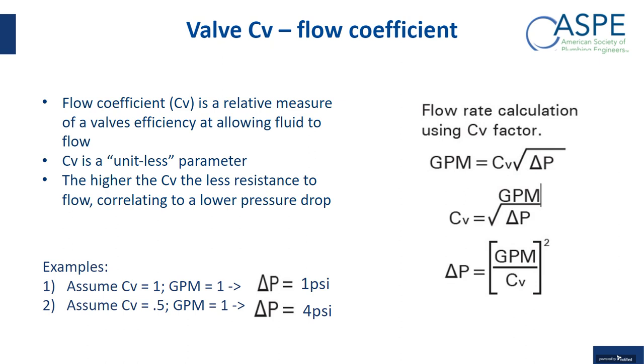These equations on the right here are all the same equation, just looking at a different variable. If you need to determine GPM going through a valve, you would need to know that valve's CV and the pressure drop of it. That GPM is the square root of the pressure drop times the CV. An example here is, let's say you had a valve that had a CV of 1 and a GPM of 1. Looking at this equation, 1 divided by 1 is 1. 1 squared is 1. So the pressure drop across that valve under those conditions would be 1 psi.